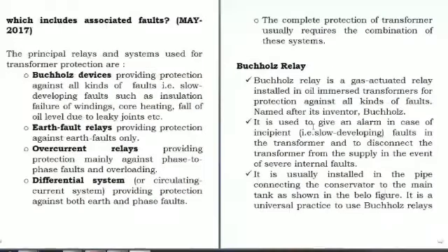The basic concept of Buchholz relay. The Buchholz device provides protection against all kinds of faults, that is, slow developing faults such as insulation failure of winding, overheating, and fall of oil level due to leakage joints like this. For all this purpose, we can use the Buchholz devices.